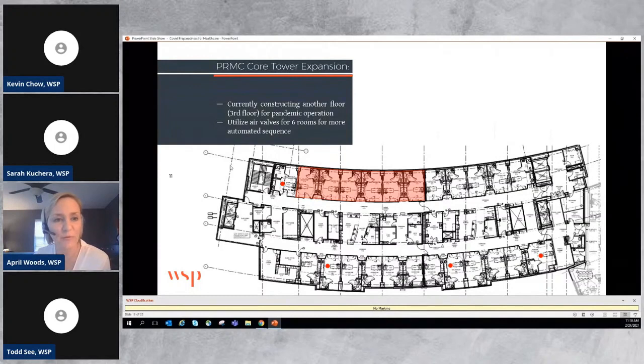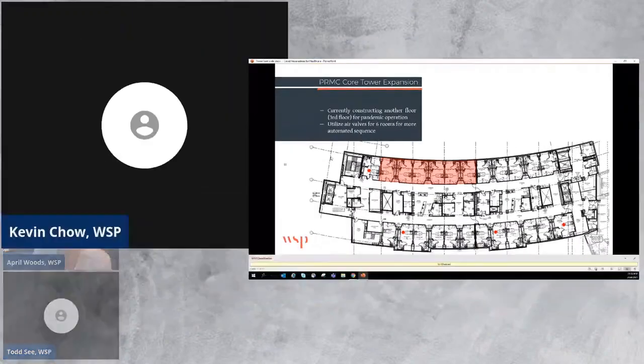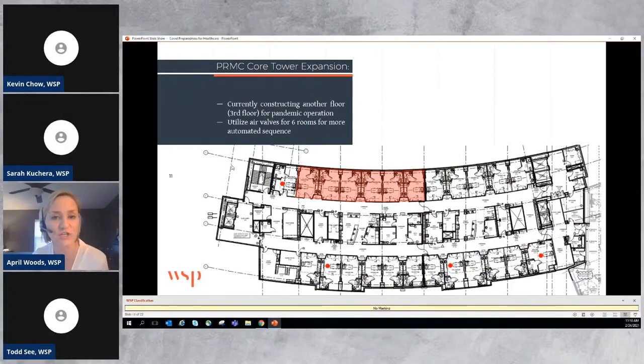One thing we did improve upon from the 6th floor that we decided to do differently on the 3rd floor is we are giving them 6 rooms that have automatic operation with the utilization of air valves to change that pressurization. And that is something we also discussed with the Department of Health, something that they will allow them to have these rooms be somewhat switchable between the positive pressure and negative pressure relationship.